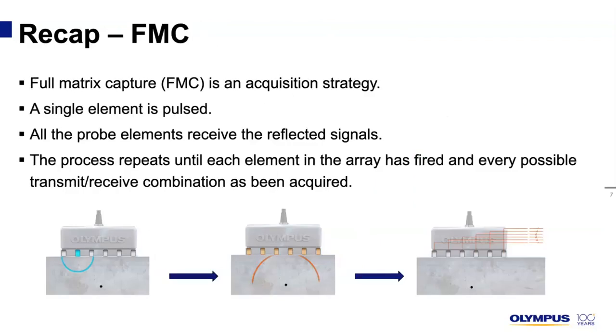FMC, or Full Matrix Capture, is an acquisition strategy. Basically, a single element is pulsed and all of the probe's elements receive the reflected signal. That's done for the first probe element and for the rest of them, and the process repeats until each element of the array has fired and all transmit-and-receive combinations have been acquired. That's what we call the FMC raw A-scans.